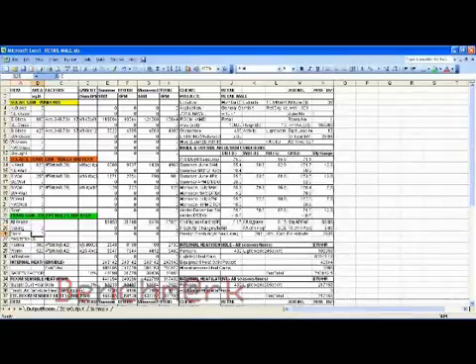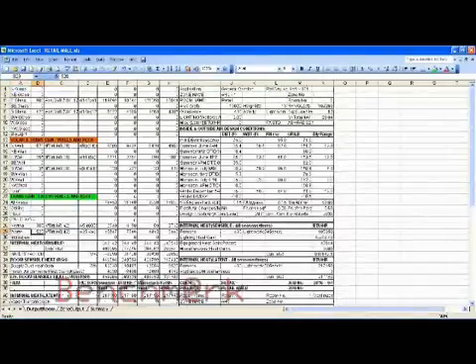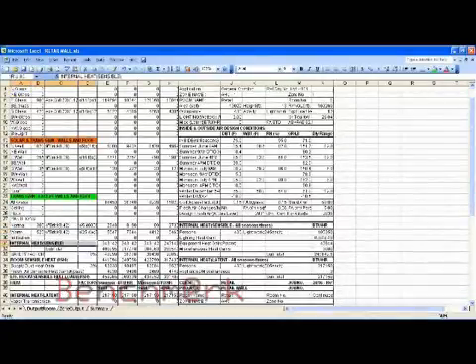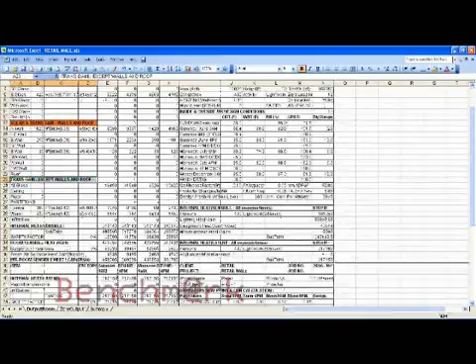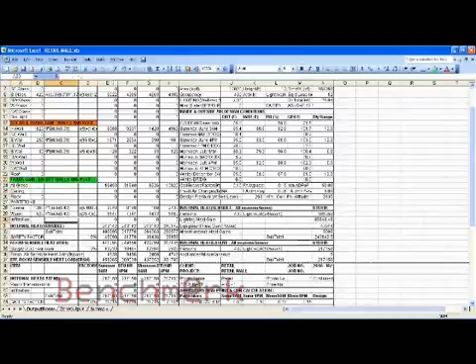With the selected ADP of 50 degrees Fahrenheit, we are getting the dehumidified CFM, room supply air temperature, room return air temperature, and the grand total heat for total tonnage in BTU per hour.